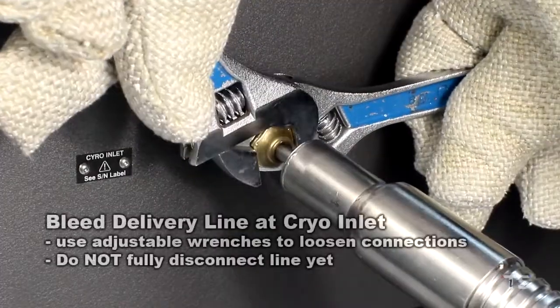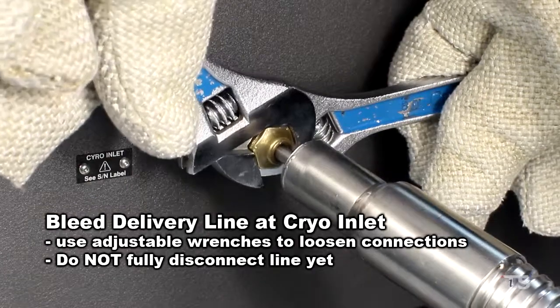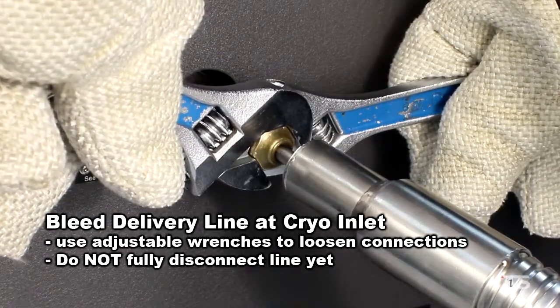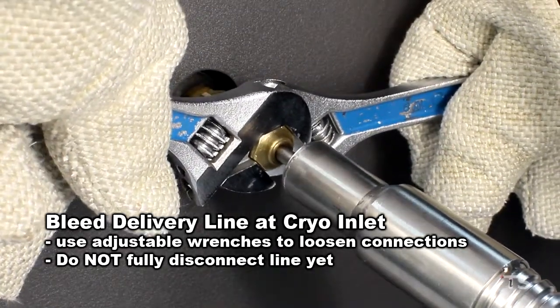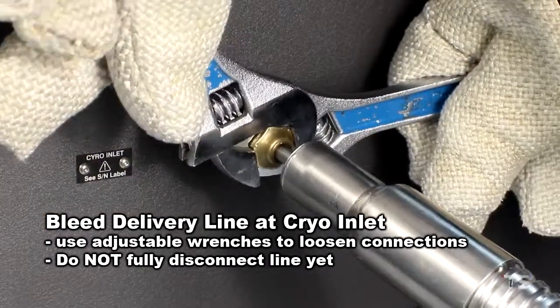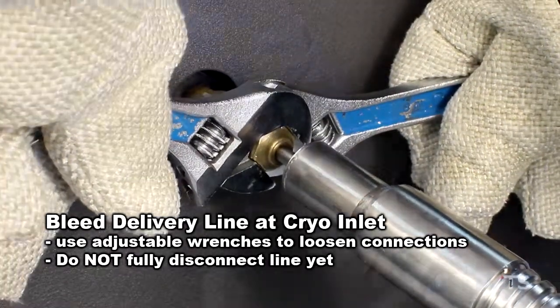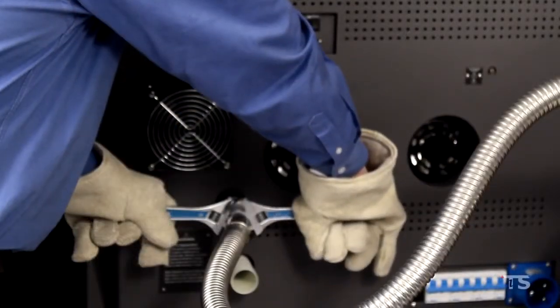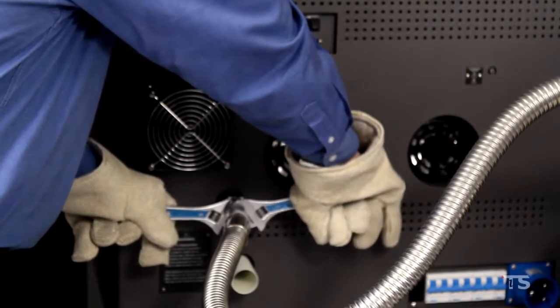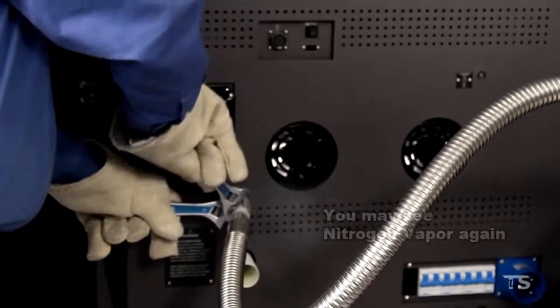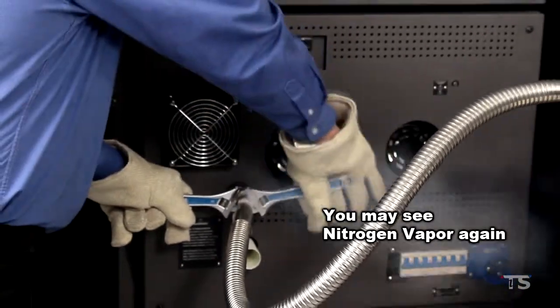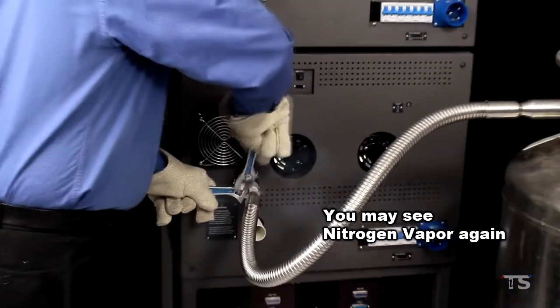Once the blue valve is closed, you need to bleed the delivery line dry of LN2. Bleed the line by using your adjustable wrenches to loosen the delivery line at the cryo inlet. Do not fully disconnect the line yet. You want the nitrogen in the line to escape as nitrogen gas. You may see nitrogen vapor when this happens, just like you did when connecting the line.